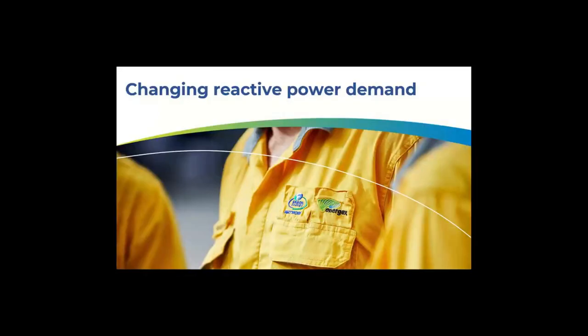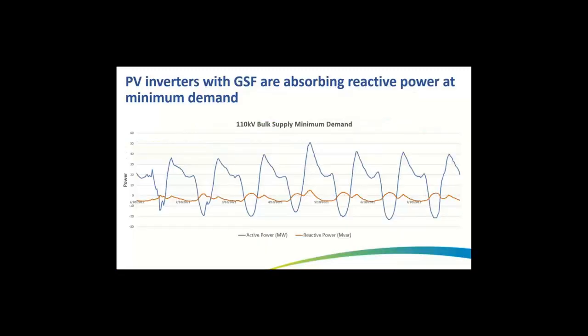This can be seen in the changing reactive power demand levels on our distribution network. Here, once again, is that bulk supply point, which we receive power from the transmission network on. And you can see during the middle of the day in blue, the reverse flows that occur quite frequently, particularly in the spring when the loads are modest. In addition, on this plot, I plotted the reactive power in orange, and you can see that often peaks in the middle of the day, and that's a result of the PV inverters now in aggregate absorbing substantial amounts of inductive reactive demand to offset some of the voltage rise associated with those reverse flows.